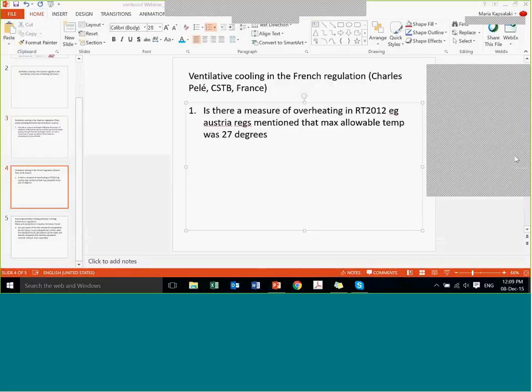And from my side, the answer is yes. It's for sure a good idea to use the air exchangers always, as long as the outside temperature is higher than the inside temperature. In case of night ventilation, I do hope that the outside temperature is lower than the inside temperature, so the air exchangers have to be bypassed. So this is our principle. We always use heat exchangers in our ventilation systems, and for night ventilation, we certainly bypass them if going for mechanical solutions.